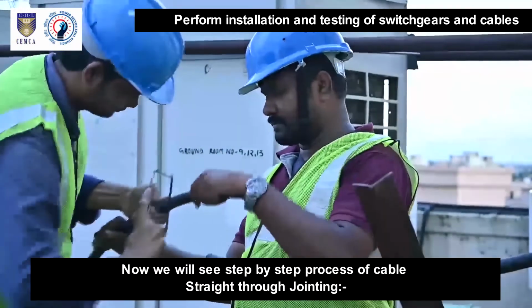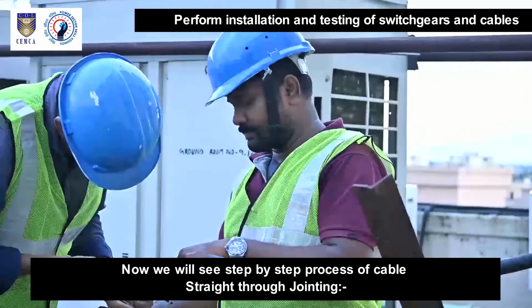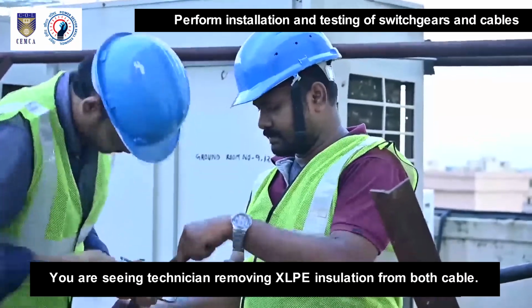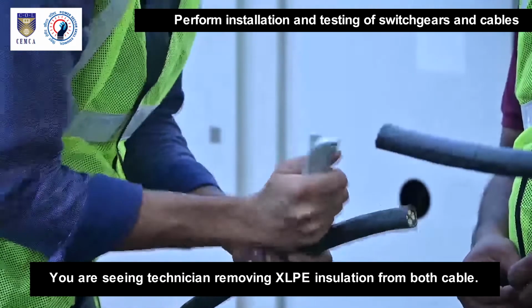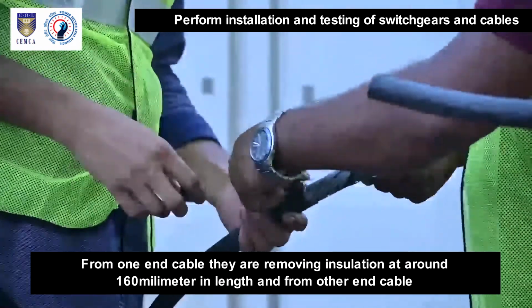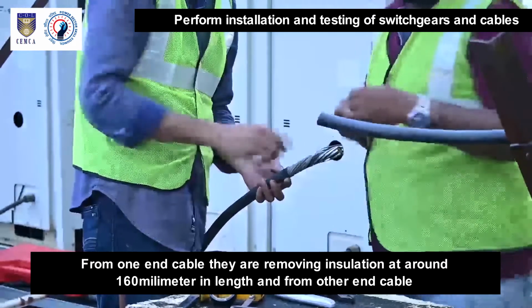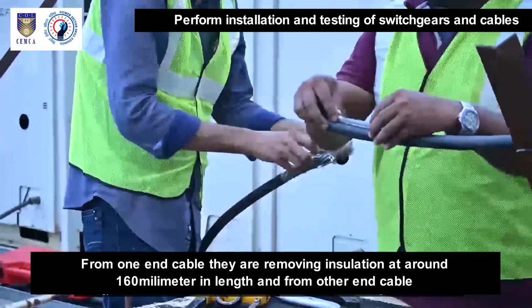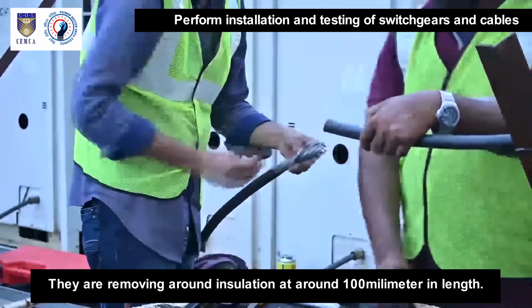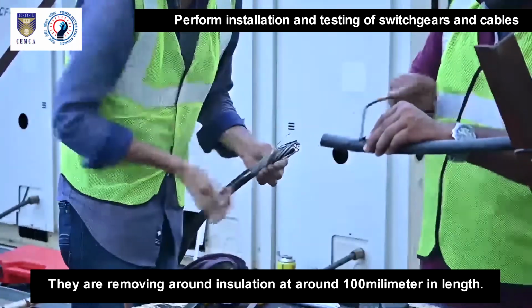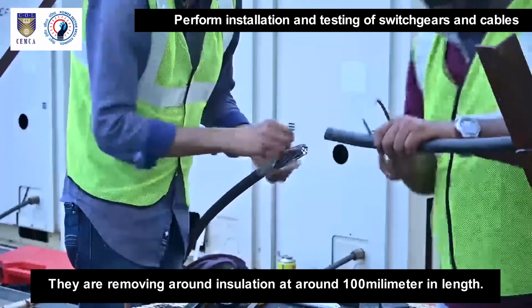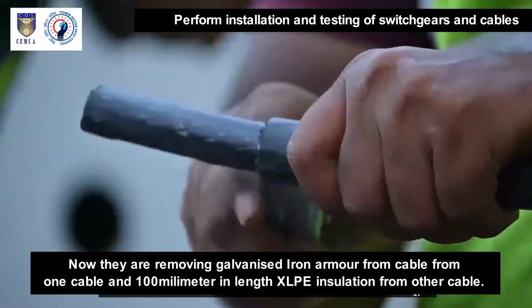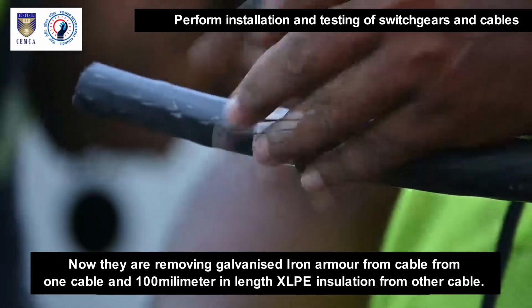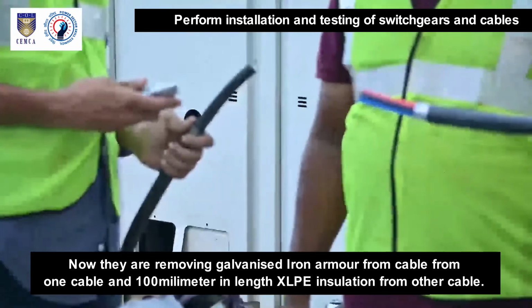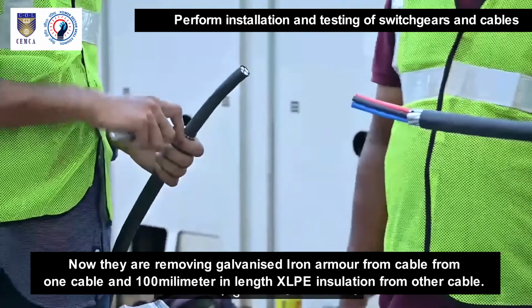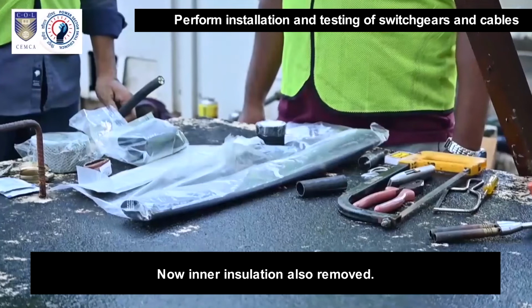Now we will see the step-by-step process of cable straight through jointing. You are seeing the technician removing XLPE insulation from both cables. From one end cable, they are removing insulation at around 160 mm in length, and from the other end cable, they are removing insulation at around 100 mm in length. Now they are removing the galvanized iron armor from one cable and 100 mm in length XLPE insulation from the other cable. Now the inner insulation is also removed.